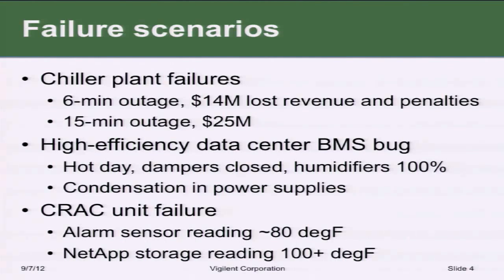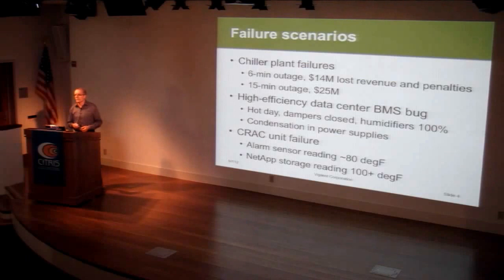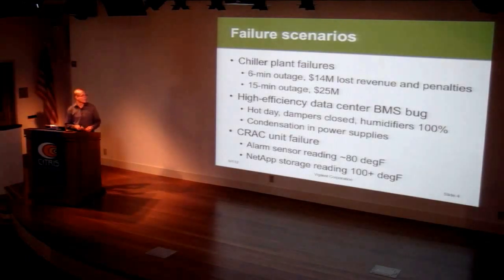Because of the energy consumption of these data centers, there's a lot of effort these days in building high-efficiency data centers of the sort that Google, Facebook, and Yahoo are building. A lot of these don't use compressors at all. They bring in outside air to cool, and if they need more cooling, they'll use spray cooling, basically glorified swamp coolers to cool the air and get the heat out.